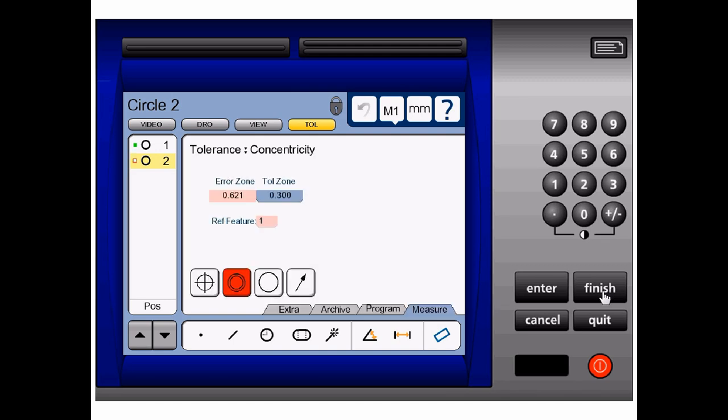You see that in this case, our concentricity has failed. It has come out at 0.621 mm and our tolerance zone is 0.3 mm. This is what is known as a failed condition. This is how you measure concentricity in the readout.